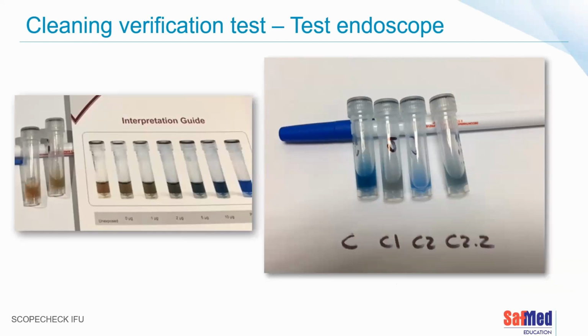These were some colonoscopes that I tested at one particular facility. The first one, C only, is the control test. There's always a positive control provided with that product, heparinized sheep's blood, used for batch testing to confirm the batch is functioning correctly. C1 was the first colonoscope I tested at this facility, which had had some issues and asked for assistance, so I went into the field to test the scopes. The C1 specimen was from the biopsy channel of one scope, and C2 was from the tip of the scope, while C2.2 was from inside the biopsy channel of that second scope. I picked up residual proteins in two of these scopes immediately, telling me those scopes had not been properly cleaned.